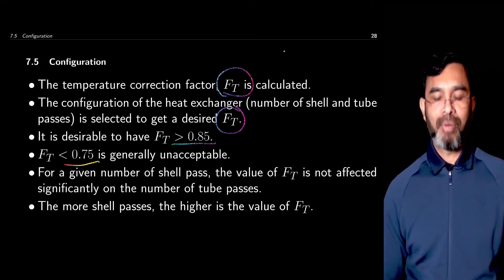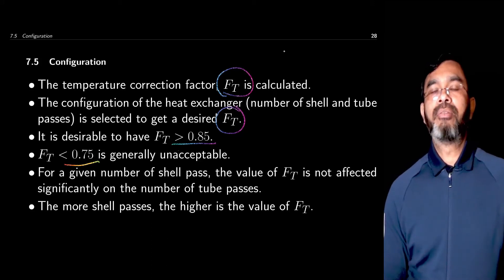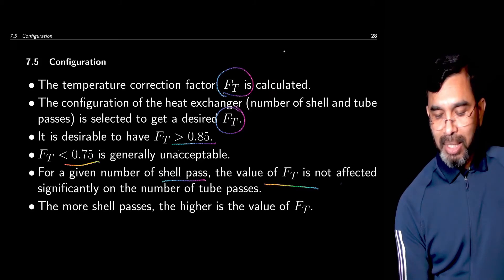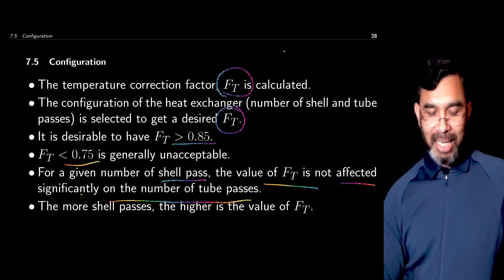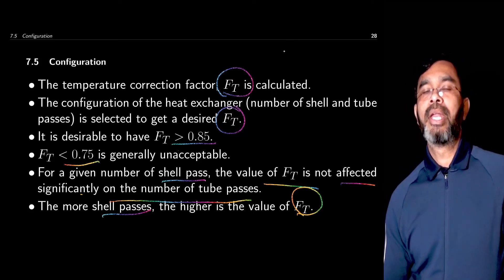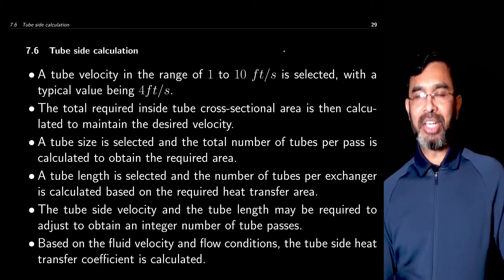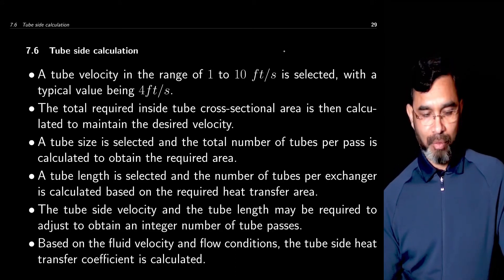If the correction factor is low — less than 0.75 — then we need to choose a different configuration. For a given number of shell passes, the value of FT is not significantly affected by the number of tube passes. So the value of FT depends primarily on the number of shell passes. If the FT value is very low, we may need to choose a higher number of shell passes. Once the configuration is chosen, we need to estimate the individual heat transfer coefficients — the tube side and the shell side heat transfer coefficients.